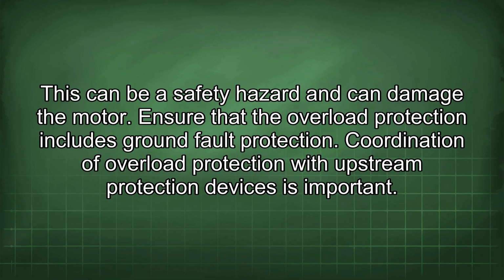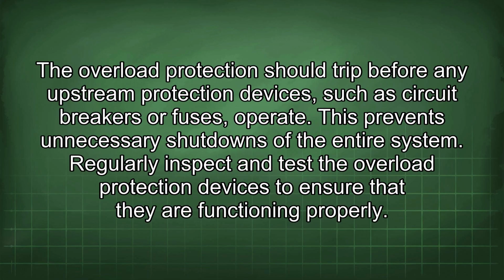Coordination of overload protection with upstream protection devices is important. The overload protection should trip before any upstream protection devices, such as circuit breakers or fuses, operate. This prevents unnecessary shutdowns of the entire system.